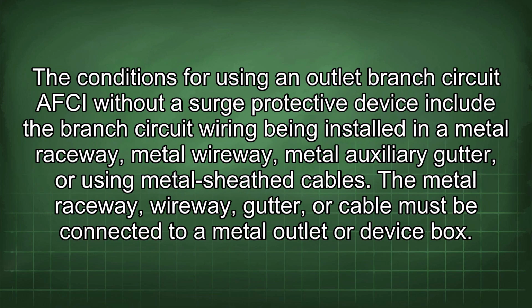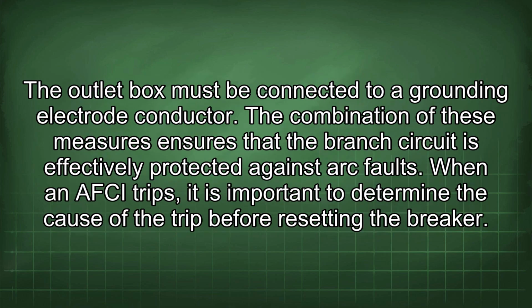The conditions for using an outlet branch circuit AFCI without a surge protective device include the branch circuit wiring being installed in a metal raceway, metal wireway, metal auxiliary gutter, or using metal sheath cables. The metal raceway, wireway, gutter, or cable must be connected to a metal outlet or device box. The outlet box must be connected to a grounding electrode conductor. The combination of these measures ensures that the branch circuit is effectively protected against arc faults.